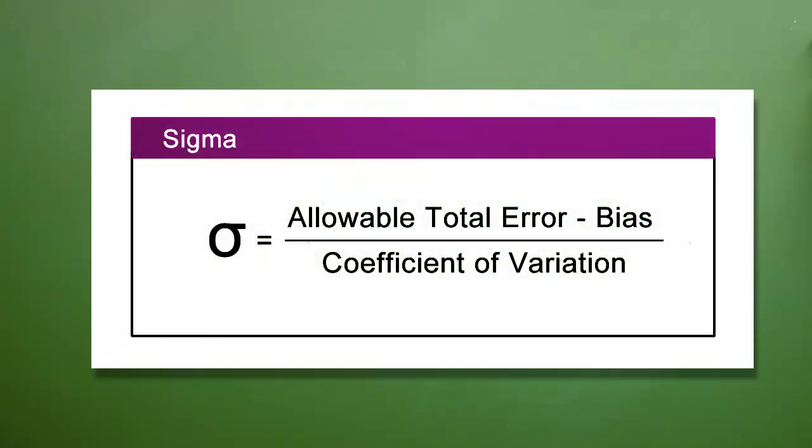Subtract your bias from the allowable total error, then divide by the coefficient of variation. We recommend viewing our previous videos if you're not familiar with the concepts of TEA, bias, or CV.